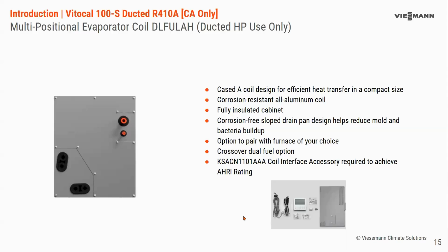And there is an additional coil interface accessory that is used to achieve the AHRI rating. What it includes is an interface that allows the outdoor unit to communicate with RS-485 to this case coil. It comes with a return and a pipe temperature sensor, as well as a wall controller. So that gives you the full modulation of the system with this case coil, and that's what is used with the AHRI listing. I will call out, however, that it is not included with the case coil and it is not technically required for operation. You can select 24-volt mode at the outdoor unit and just communicate directly with the thermostat in the furnace. However, you will not have the full range of modulation that you would have when you use this accessory coil interface. And the widths available are 14.5, 17.5, 21, and 24.5.